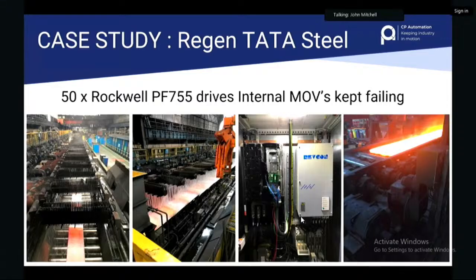There were 50 of these in total, and I think it got to the point that 7 had failed before the customer finally said, okay, what can we do about it, and called us in. Because we supplied the regen units, and the regen units weren't failing, they said, what's different? I said, well, we've got better protection inside our regen units than the drives. And they said, how? Well, I said, really, in effect, it's got a sine tamer inside.